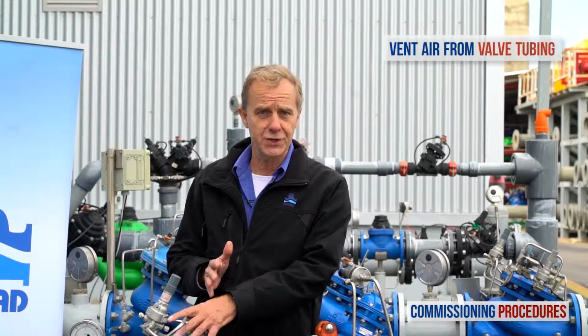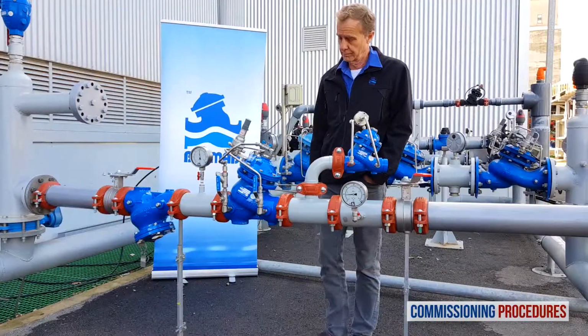Whether or not you performed recalibration, the next step is to remove any residual air from the pressure reducing valve's control loop and the chamber. This ensures a more stable and positive pressure control.